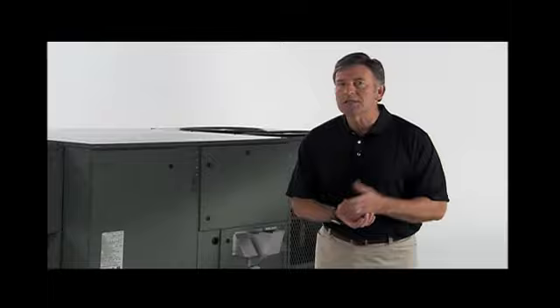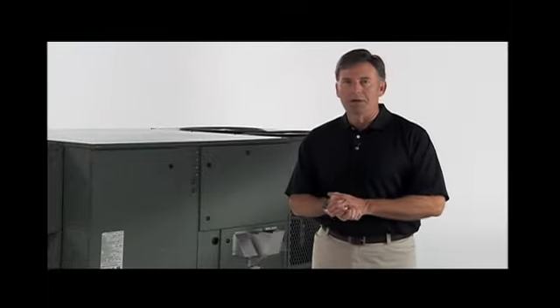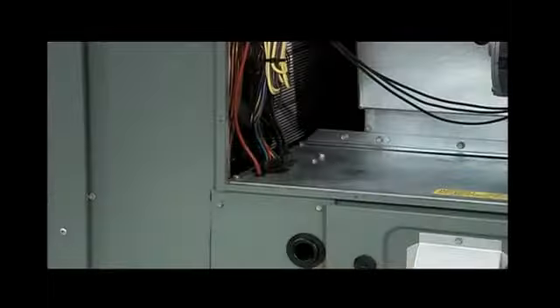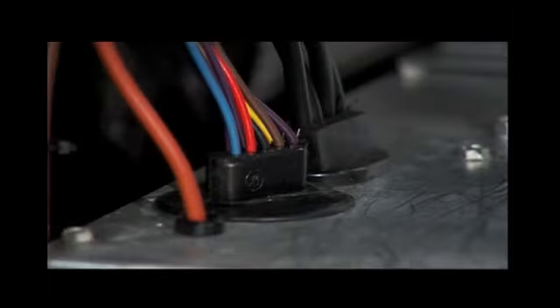Also inside the blower compartment is the low ambient control, low pressure switch, high pressure switch, and freezestat safety devices. The low ambient control allows for operation of the compressor down to 0 degrees ambient temperature by cycling the outdoor fans on high pressure. The high pressure switch will shut off the compressors if pressures in excess of 610 psig are detected. This may occur if the outdoor fan motor fails. The low pressure switch shuts off the compressors if low pressure is detected due to loss of charge. The freezestat protects the compressor if the evaporator coil gets too cold due to low airflow or low load.